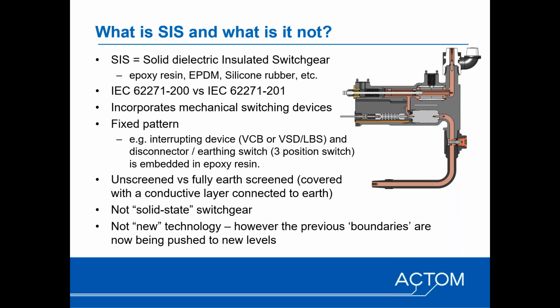The other thing to note is that solid dielectric switchgear incorporates mechanical switching devices, so it does not mean that it uses solid state. A lot of people initially assume when we talk about solid dielectric that it might imply solid state switchgear, and that's not the case. Solid dielectric insulation effectively refers to the insulating medium, not the type of interrupting medium, as covered earlier. So you would typically have an interrupting device, which could be a vacuum circuit breaker, a vacuum switch disconnector, or a load break switch, as it is commonly called in US terminology, as well as a 3-position disconnector, all embedded in epoxy resin, and then, as we'll talk about later, covered by an earthed conductive screen.